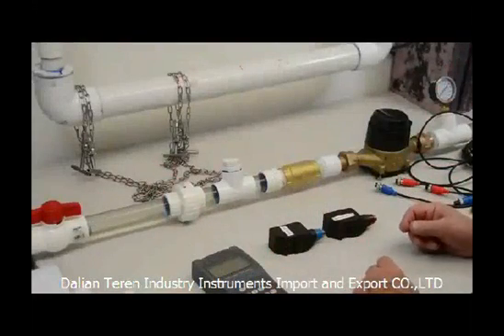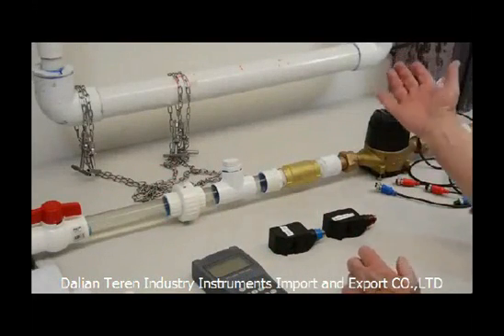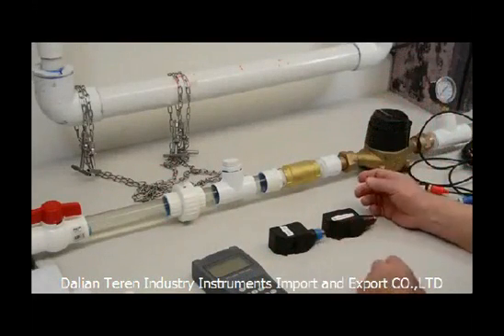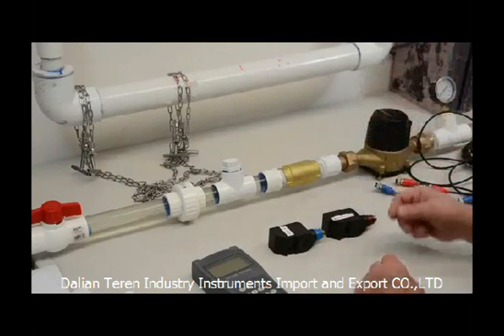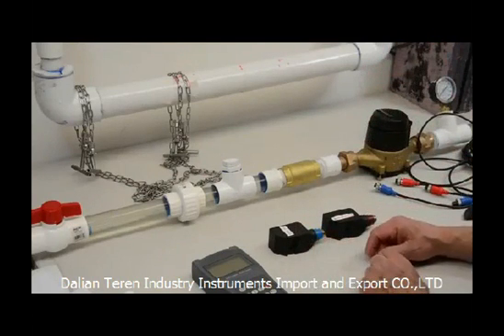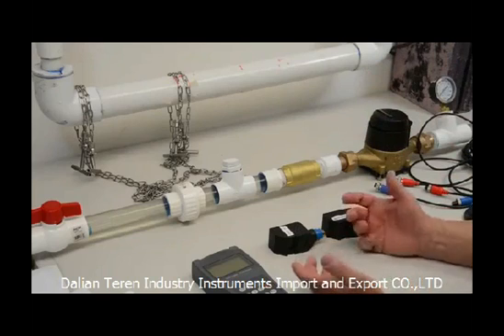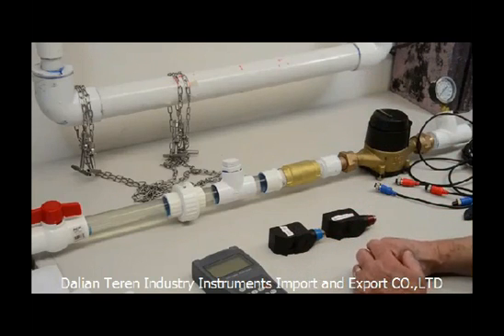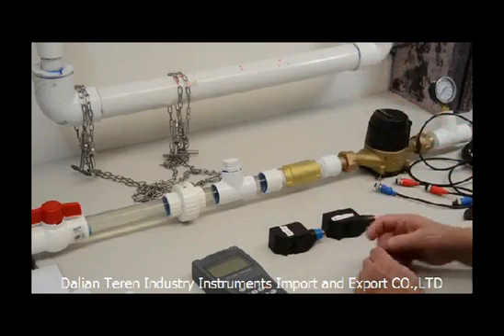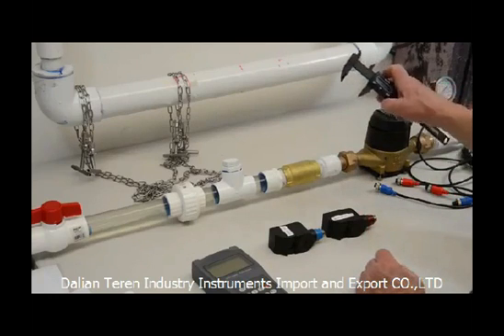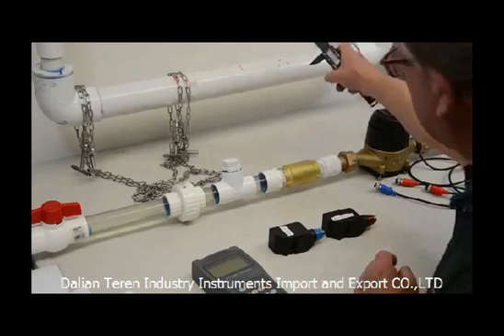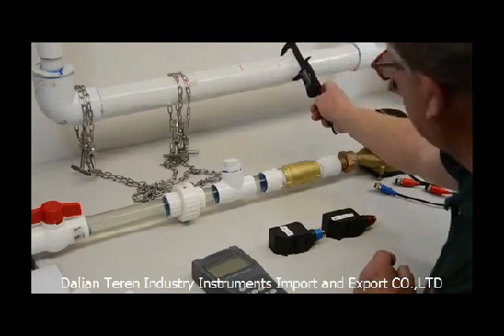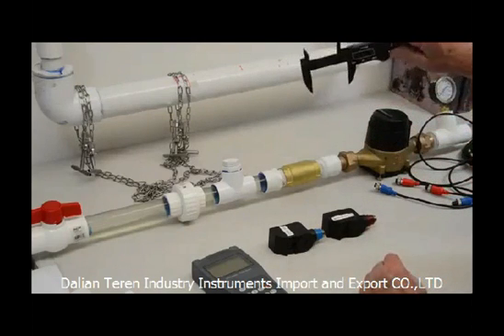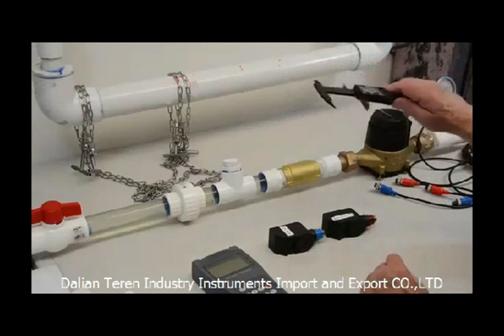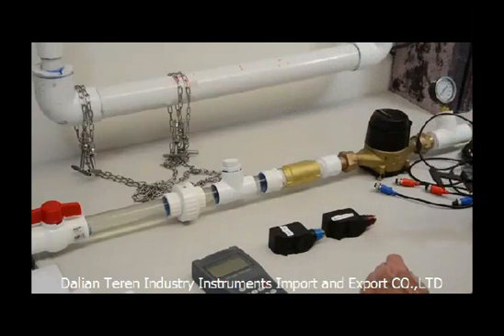This is part of our test bench where we calibrate every single meter before we send it out. I'm going to use two M1 transducers, which are for 2-inch pipe and above. And so here's my 2-inch pipe. The first thing I want to do with any pipe is to use my calipers or whatever I need, and I can measure it. In this case, it says my 2-inch pipe is 2.38 inches.